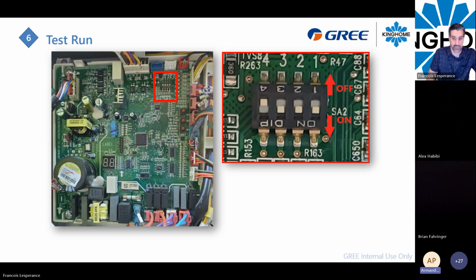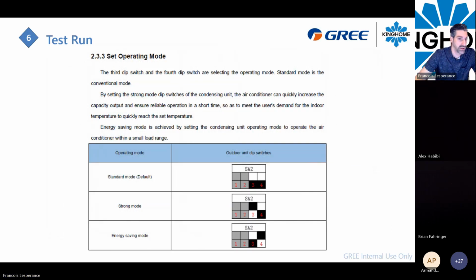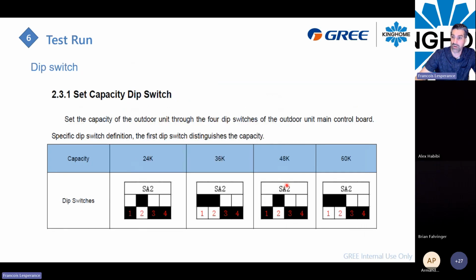Okay, so why do we not use the 5-ton unit with the 4-ton coil, and switch from the 4 to 3.5? If you're using a 4-ton unit, then you will have only the option to use it as a 5-ton or a 4-ton. So you will have the same dip switches here, but if you have the cabinet with the 2 fans, the 5-ton cabinet, you can set it as a 4-ton, and you can also reduce the capacity a little bit, so it can be a little bit less than 4-ton.